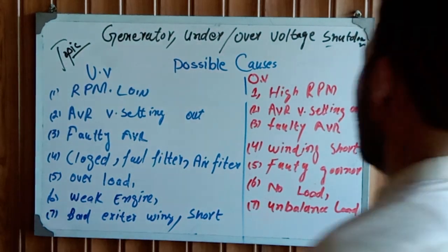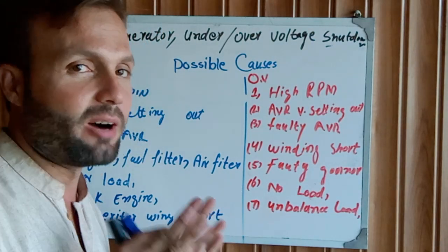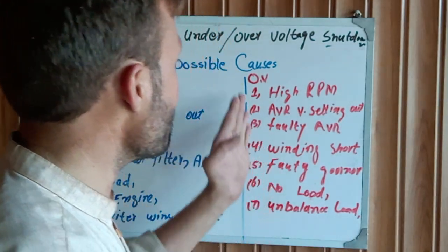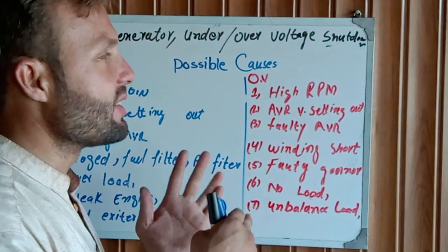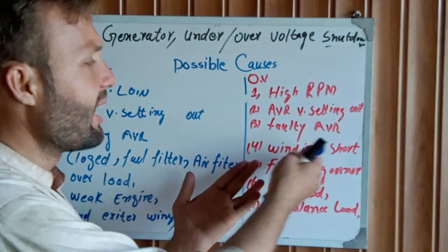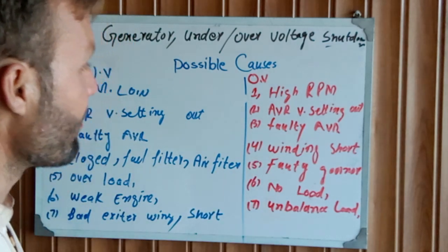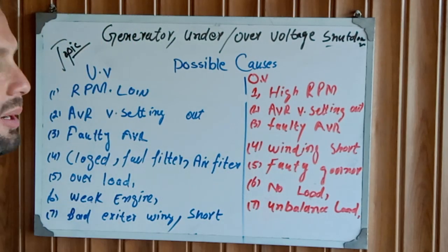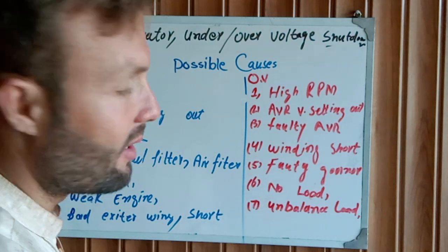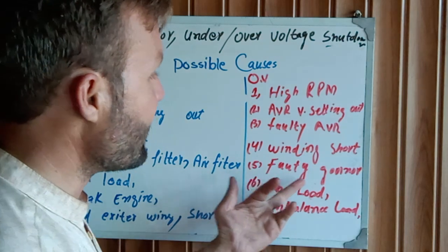Another cause of over voltage is a faulty AVR. If your AVR is malfunctioning or is a bad AVR, this means your voltage is raising uncontrollably. Swap it out — install a new one and check the problem.